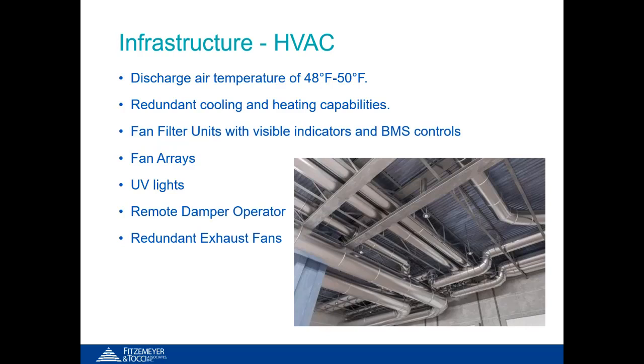Fan arrays can provide increased redundancy and reliability if additional static pressure is required, as these can easily be retrofitted into existing units. Placing UV lights located on the discharge face of the cooling coil will provide control of microbial buildup and contamination in the airstream. This is commonly provided to ensure pure air is delivered to the space. However, with the current pandemic, they're more and more common to provide healthy, clean air to the general areas as well.